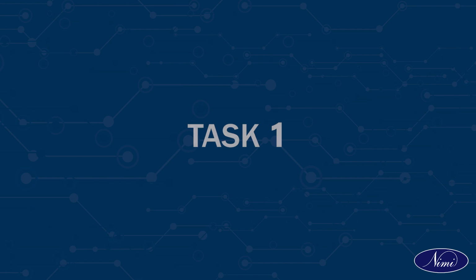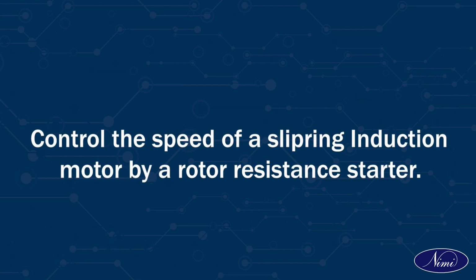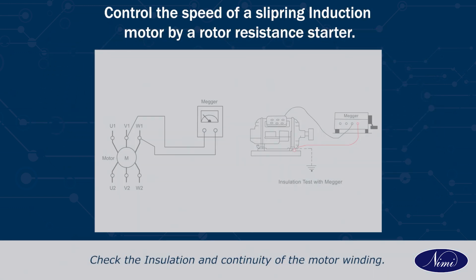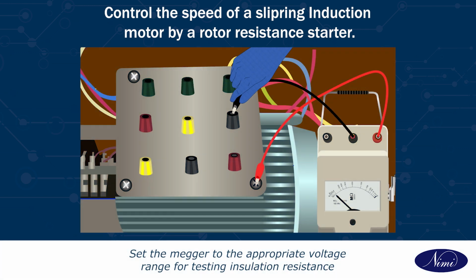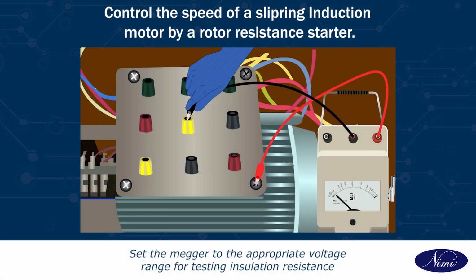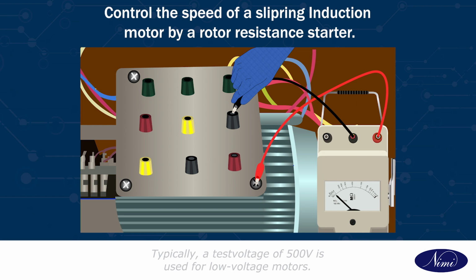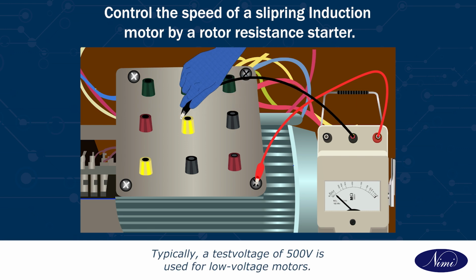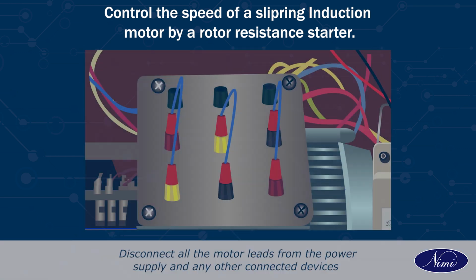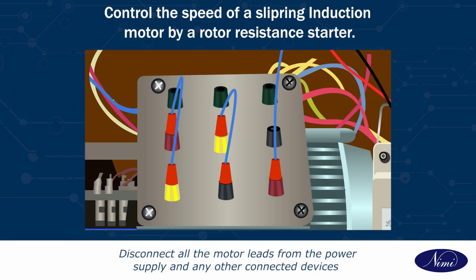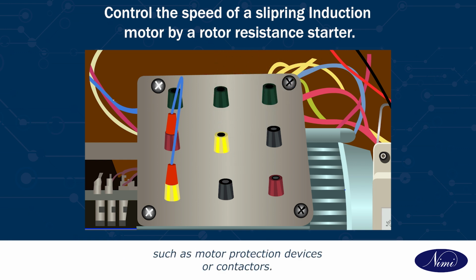Task 1. Control the speed of a slip-ring induction motor by a rotor resistance starter. Check the insulation and continuity of the motor winding. Set the megger to the appropriate voltage range for testing insulation resistance. Typically, a test voltage of 500 volt is used for low voltage motors. Disconnect all the motor leads from the power supply and any other connected devices such as motor protection devices or contactors.